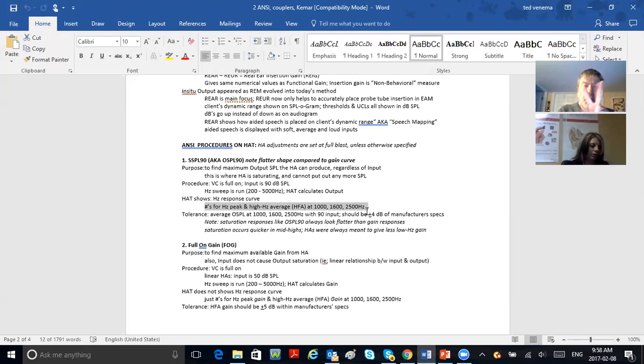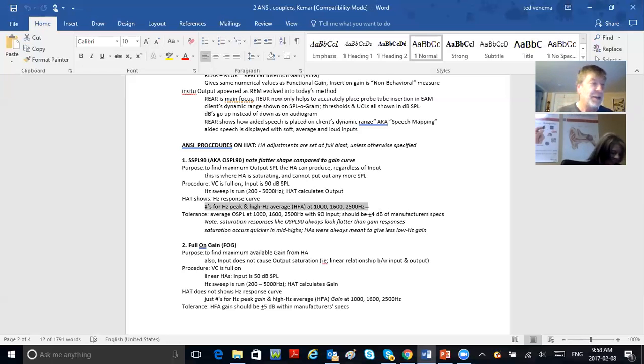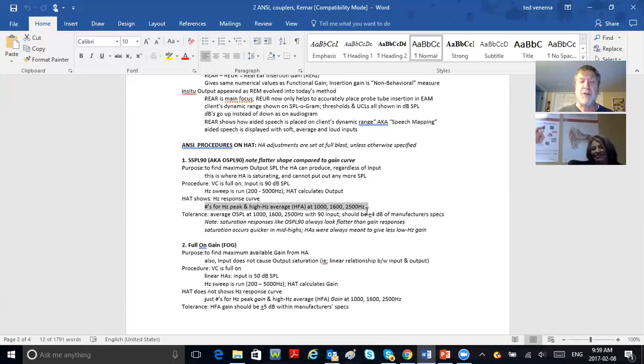Number two: full-on gain. The purpose is to find the maximum available gain from the hearing aid—no longer the output. Procedure: volume control still full blast. For linear hearing aids the input is 50, but almost no one uses linear hearing aids anymore; most use compression. A frequency sweep is run, and the hearing aid calculates the gain.